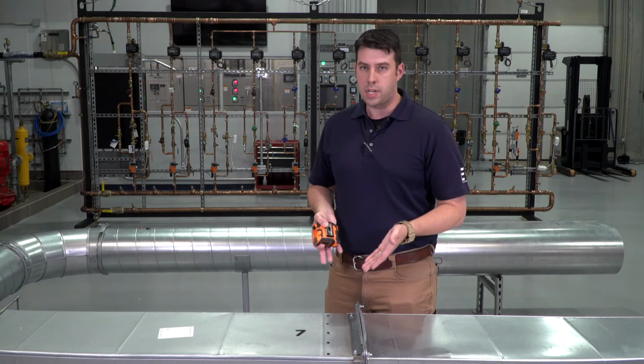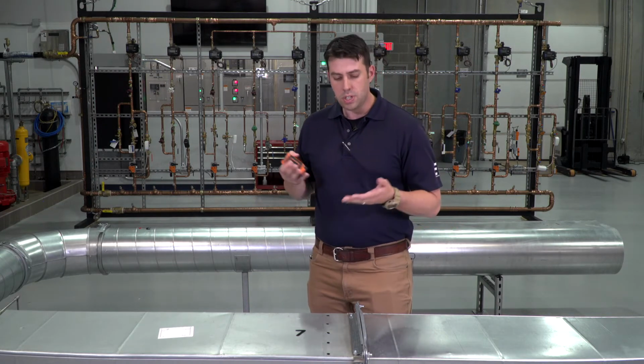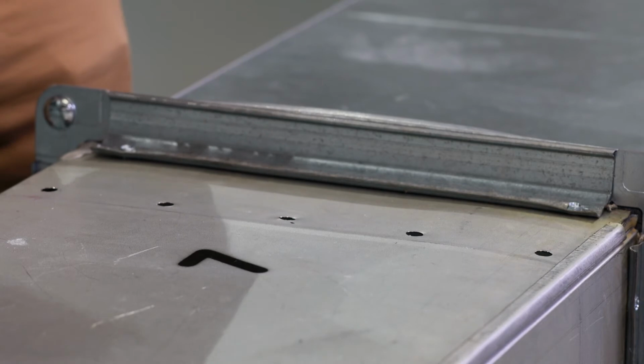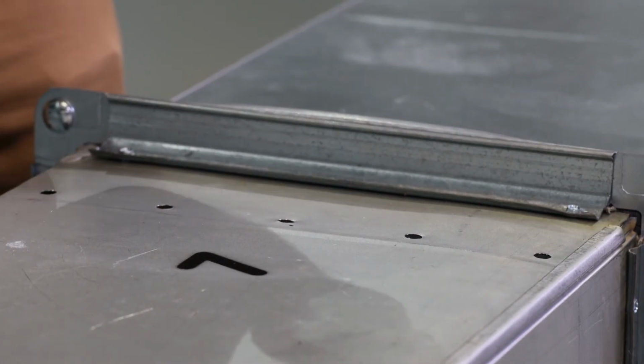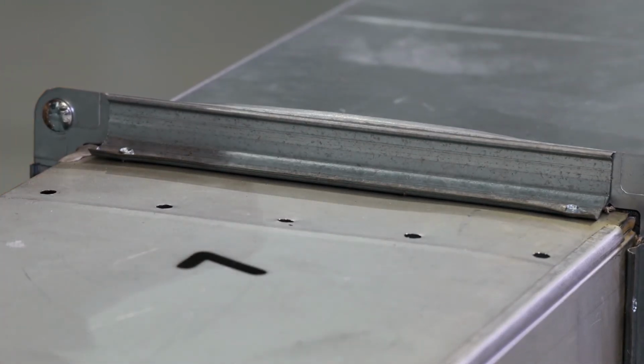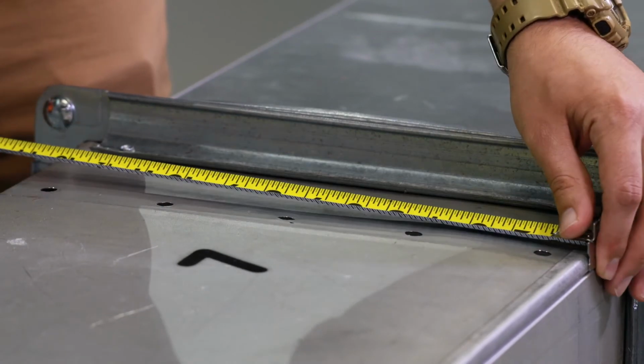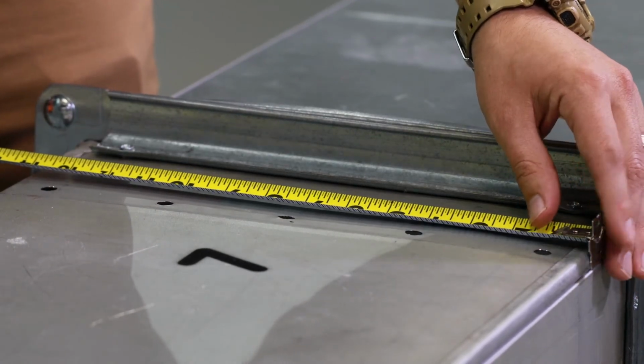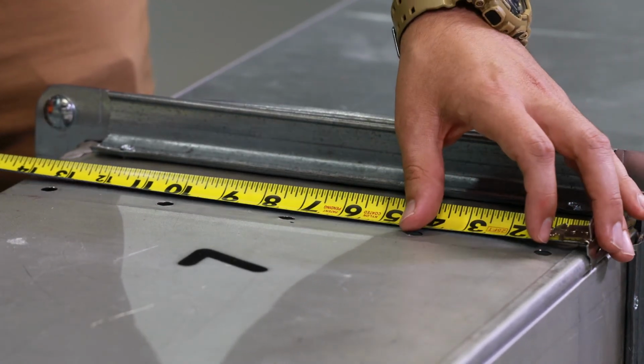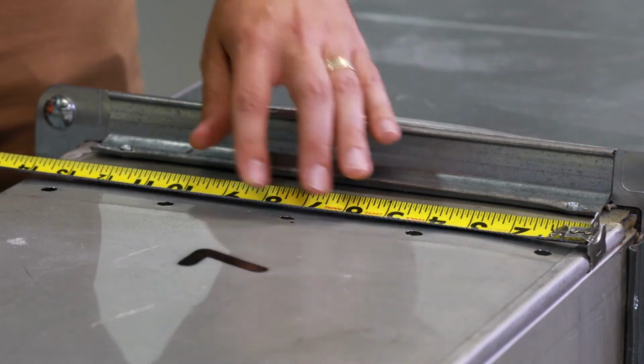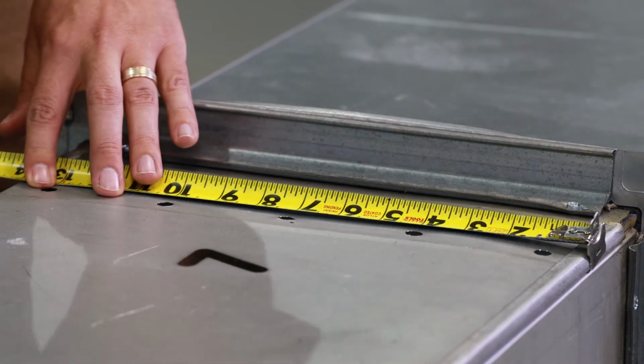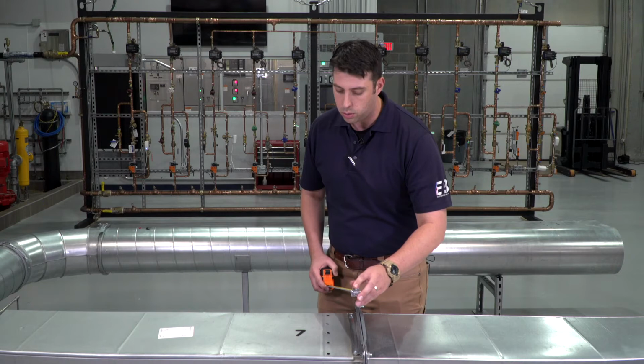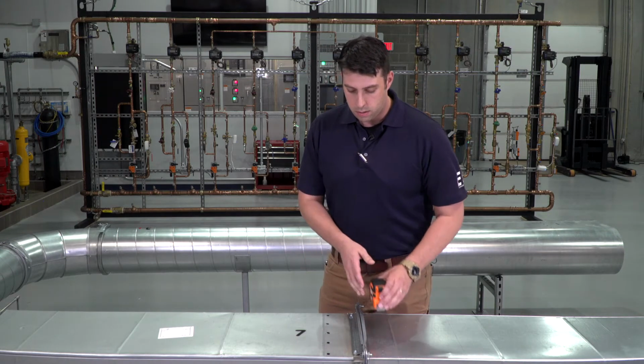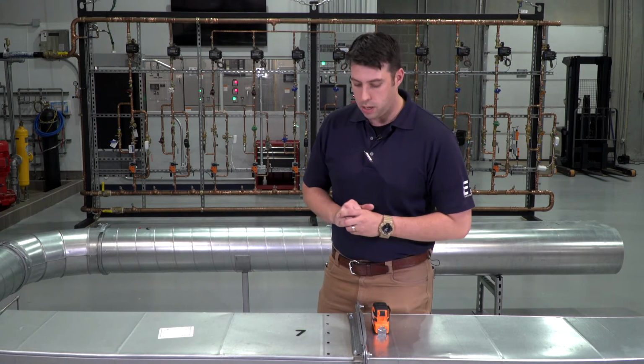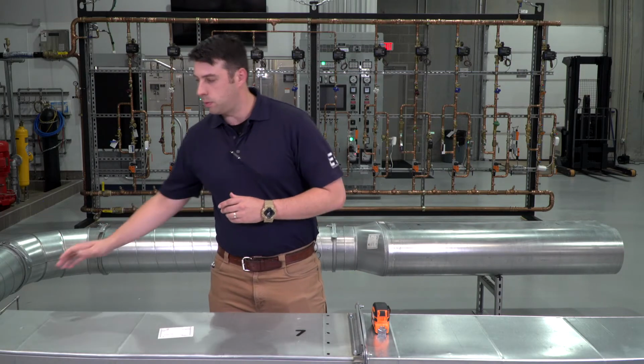This is a 14 by 14, as we previously mentioned. So it just so happens that the same markings we had on our pitot tube are going to be marked here on our ductwork. And just for quick reference, we had a 1-inch hole, a 4-inch hole, 7-inch, 10-inch, and 13-inch markings for our 3/8 inch holes. So our next step is going to be utilizing the pitot tube and hooking up with the manometer.